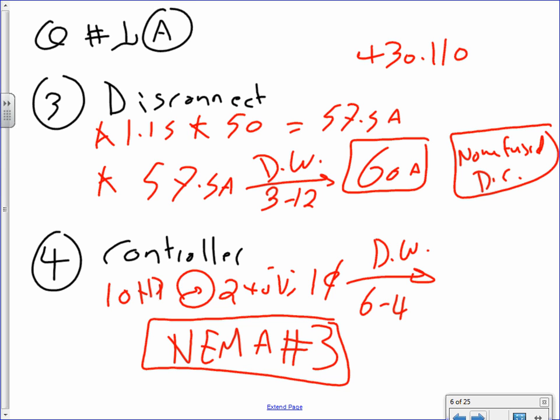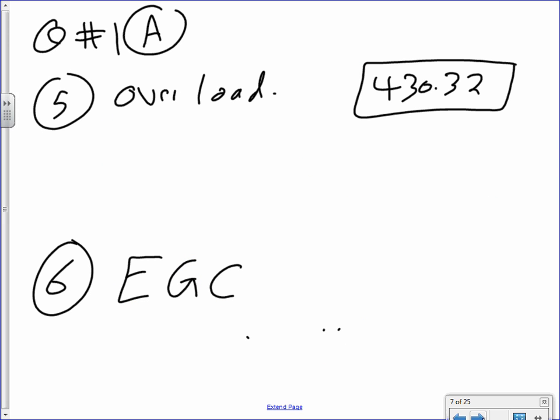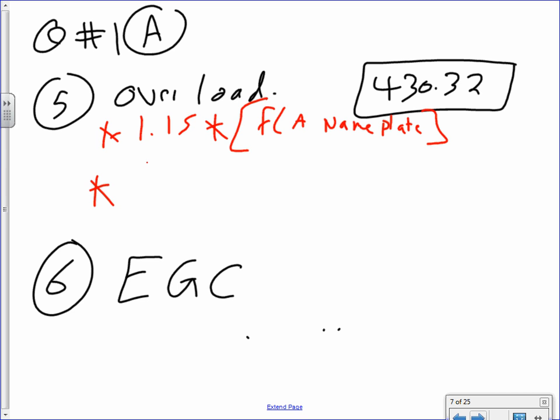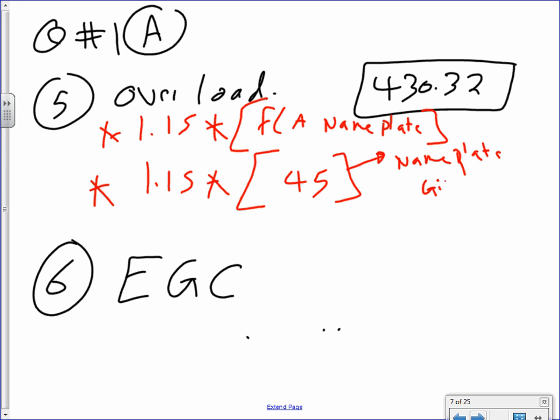Overload. The next one is overload. For overload, you go to 430.32. We have been there. You're going to take 1.15, because we have no idea what the service factor is, times the full load amps on the nameplate. The nameplate is given. I'm giving you, it's 45. Did you hear me? And when you do this, it ends up with 51.8 amps. So your overload will be set at 51.8 amps.